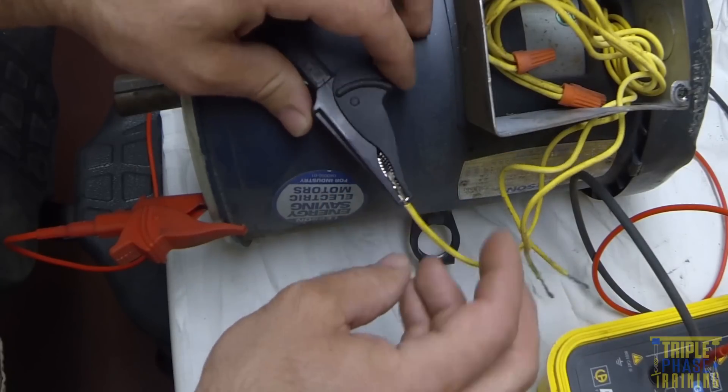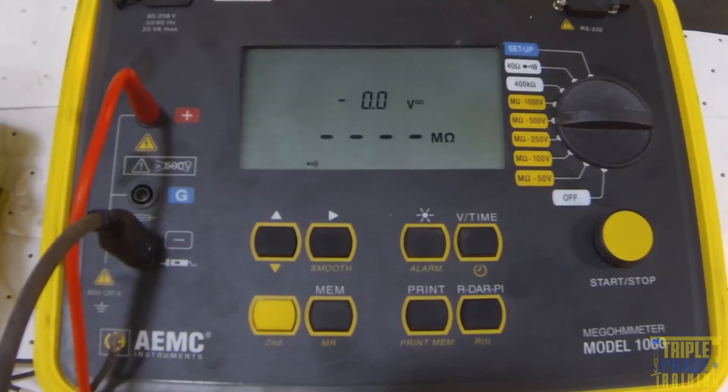You must select the voltage range on the meter that matches the motor you are testing. This is a 480 volt motor, so the dial is set to a 500 volt test.